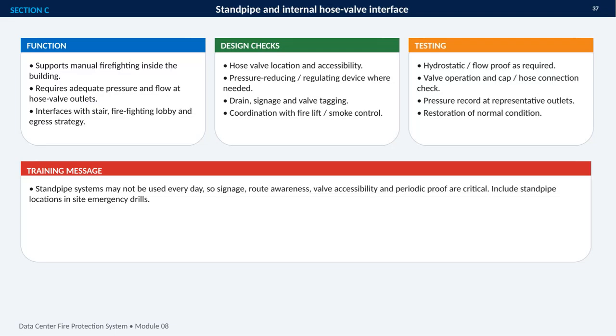This section focuses on the standpipe and internal hose valve interface, which supports manual firefighting inside the building. Its effectiveness depends on having adequate pressure and flow at the hose valve outlets, while also fitting into the overall stair, firefighting lobby, and egress strategy. The design checks are practical but essential.